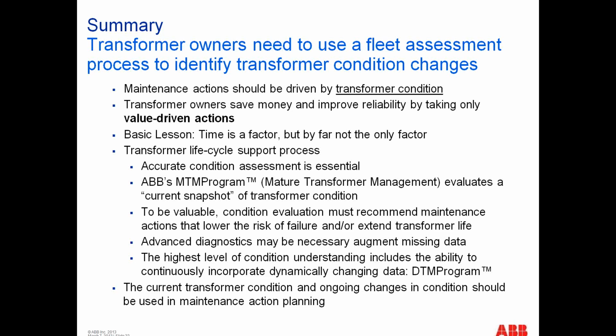As I mentioned, there's a lot of statistics showing that tap changers that are serviced and re-energized have a big percentage contribution to the tap changer failure pool. Anytime you touch your transformer, it's hard to believe, but it's a precision piece of equipment. Anyone who's been to a factory that manufactures large transformers knows it's almost a clean room environment. Particles are key. If you open up your transformer, you always risk moisture and other contamination, and you need to treat it as such.